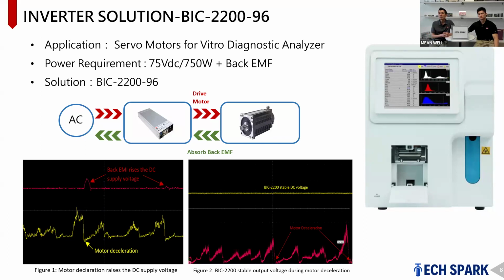So on the slide here, we have two oscilloscope photos. On the left hand side, you see the DC voltage bus of the AC to DC power supply. The yellow curve is the motor current. When it's ramping down, you see the red spike on the voltage. That's where the back EMF is generated and fed back to the DC power supply, causing it to go into overvolt protection. And on the photo on the right here is where the customer put the BIC 2200 in the system and tested. You see the yellow line is basically a straight line, with no spike.